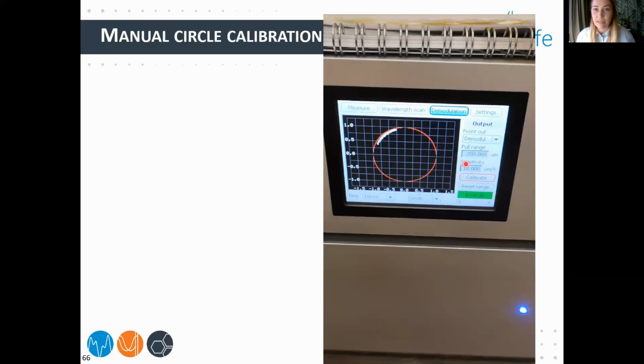So usually if you did the calibration at a different temperature, then your signal will drift away and you need to recalibrate this demodulation signal. And as you saw, you can do that in 30 seconds, just simply tapping on the system or somewhere close to the probe, so inducing some noise, and then your signal is back on track.